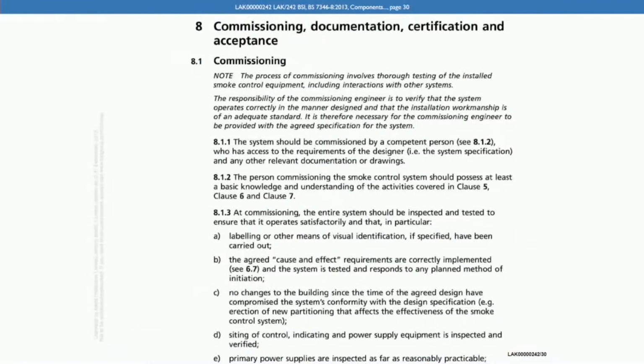It says it's therefore necessary for the commissioning engineer to be provided with the agreed specification for the system. And then if we look at clause 8.1.1, it says below that the system should be commissioned by a competent person, see 8.1.2, who has access to the requirements of the designer, i.e. the system specification, and any other relevant documentation or drawings. And then below that, it says at 8.1.2, the person commissioning the smoke control system should possess at least a basic knowledge and understanding of the activities covered in Clause 5, Clause 6 and Clause 7. That's of this British standard.